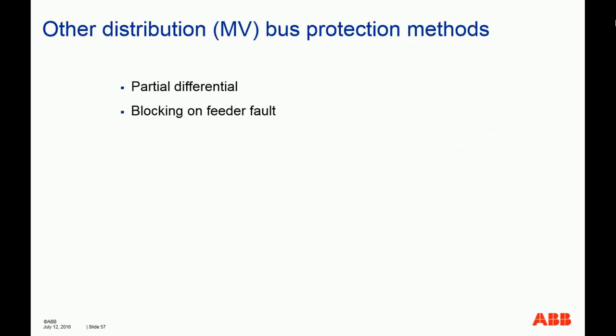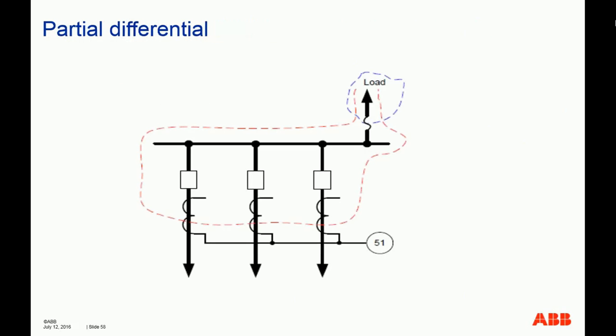So other types of bus protection methods are partial differential, blocking, or feeder fault. So what is partial differential? Partial differential usually means you actually group the sources typically together. Okay, so I guess this arrow was drawn incorrectly. So these are sources, these are the load. So you usually group the sources together and connect them to the overcurrent. The reason that you do that is that these 3 sources become one.